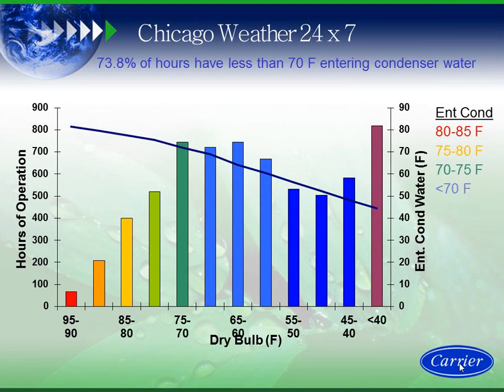If you look here at Chicago weather, and this is very similar for both Chicago and Milwaukee, if you have a building that operates 24/7, 73.8% of the hours can operate with less than 70 degree entering condenser water temperature. And the reason why that is good, and this is a major piece, is that when we talk about chiller efficiency, it's all going to be related to what we call lift. You're going to hear me talk a lot about lift throughout the presentation.